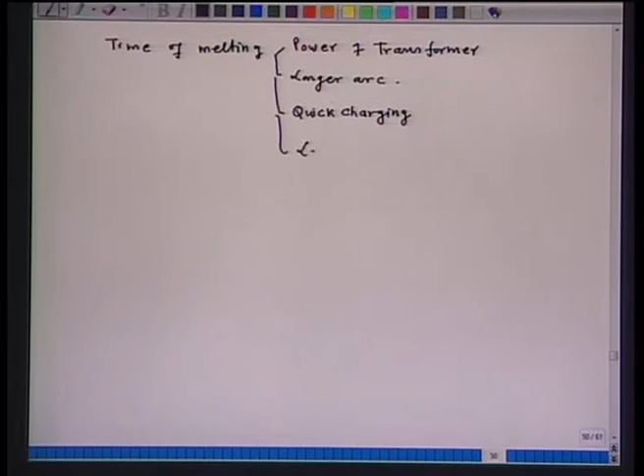Now, larger electrode spacing decreases the meltdown period, because the arc encompasses a larger scrap area. But too large a spacing means you will be too near the walls, and accordingly the walls of the furnace will be affected. So, an optimum has to be struck. A deep bath and relatively narrow shell also shortens the meltdown time.